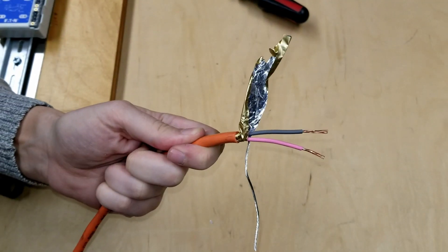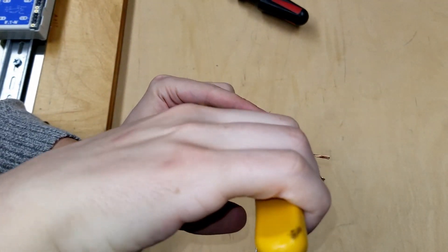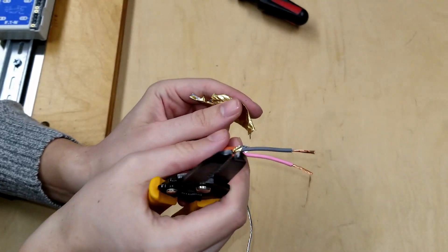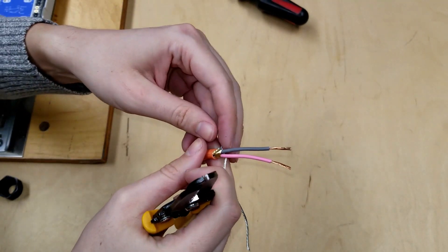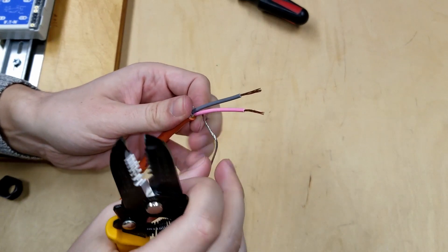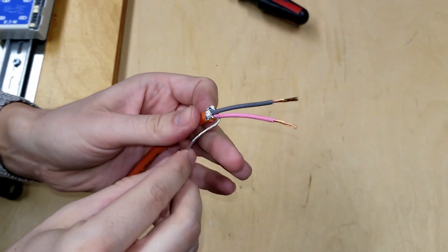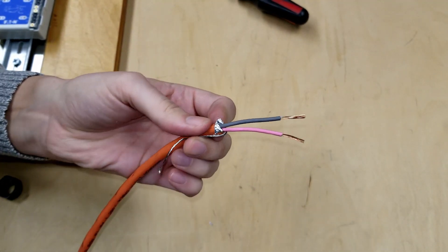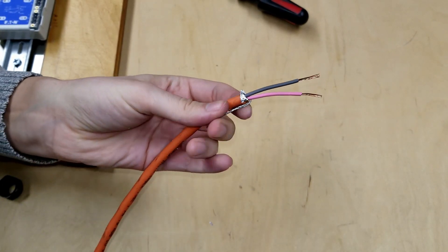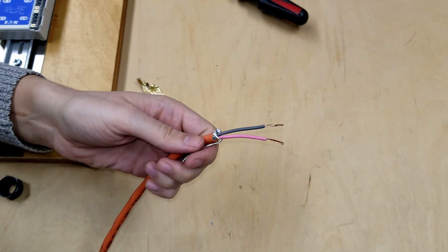Now we'll see how to properly prepare the Fieldbus cable for the instrument. Start by cutting off the excess foil. Then take the shield drain wire, make sure it's not too long, and fold it back along the jacket of the cable.